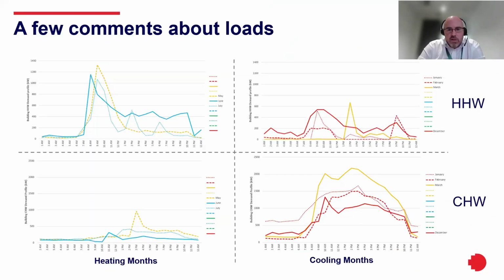And important when you're considering simultaneous heating and cooling is to understand where the load profiles occur relative to one another. You can see the heating, which is in the blue because it's cold, is the peak heating is about 1200, where if you look across to the cooling requirement, the peak is about 2.2, 2.3 megawatts. Why that's important is when you think about electrical capacity, which is a big concern, there's no simultaneous heating and cooling capacity in the building generally that would overlay an electrical requirement for simultaneous heating and cooling at the same time at significant capacity. So if you've got 2.3 megawatts of electrical equivalent for your cooling, you've got a large chunk of what you need for your heat pump during the winter when your chillers are not operating, generally speaking.